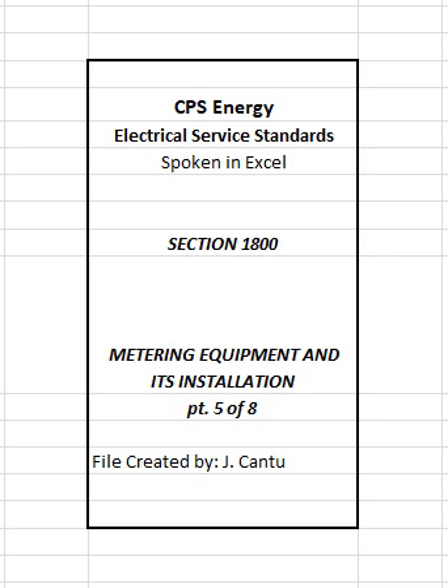1807.2 Minimum spacing between metering equipment and adjacent equipment. Spacing for self-contained meter sockets shall be a minimum of 1 inch on sides and 2 inches at top and bottom of socket enclosures. For transformer-rated meter sockets and instrument transformer enclosures, spacing shall be a minimum of 2 inches on sides and bottom and 8 inches at top.